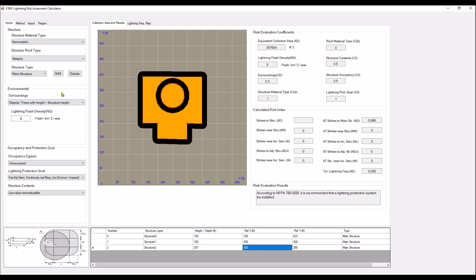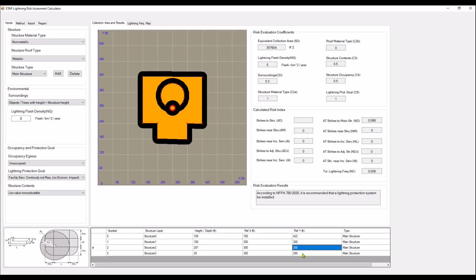And then we have the bronze, which is basically the Statue of Freedom, which is 19.5 feet. We could add that as a particular structure on top of this, which could be, in this case, probably 10 feet in length. And adding it to that particular case will give me almost 20 feet of height. And we could add it to a different y coordinate, which is going to be your corresponding selection of that particular statue. So if the lightning strikes in this location, there would be a different assessment compared to the way it strikes in this particular case.